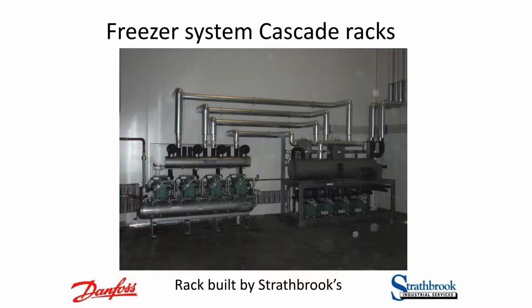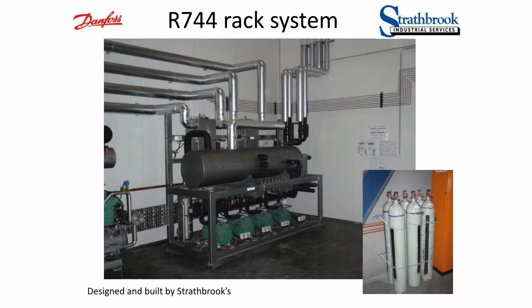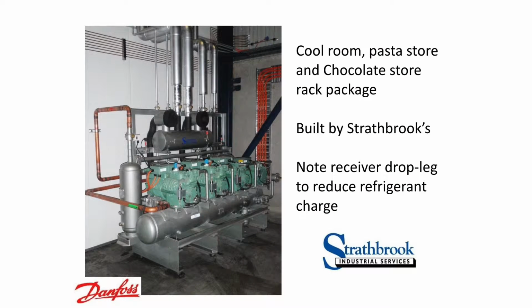So there's the refrigeration plant for the freezer. You can see on the right hand side is the low temperature CO2 machine, and then it's directly coupled to an R134A machine that's taking heat from the CO2 and getting rid of it out through an air-cooled condenser outside. There's the low temp machine, and then the cool room machine. As you can see, this is all pretty standard stuff you would have seen in a supermarket at that time in 2011. We did what we could to reduce the amount of gas in the things.